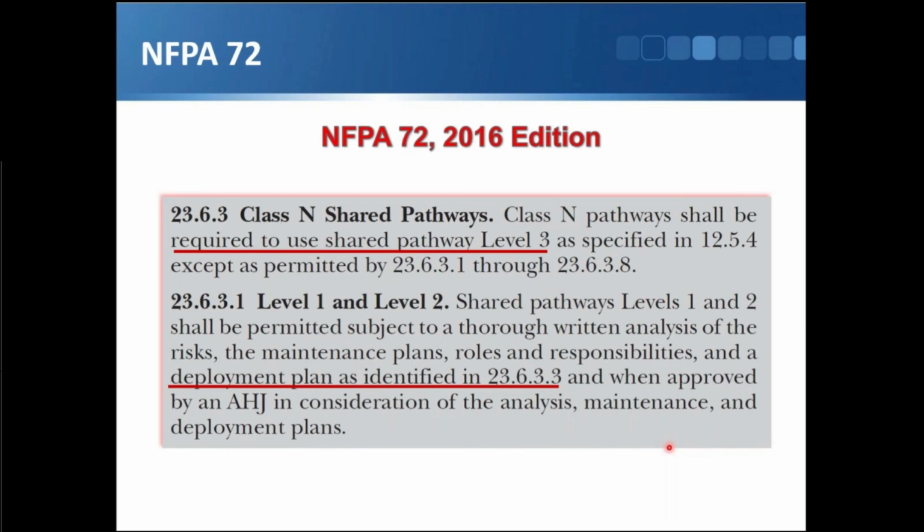All right, so here, in chapter 23, this is where they talk about the SLC circuit basically. So it's other sections that point to these other requirements that were in chapter 12. Here it says that Class N used for the equivalent of the SLC between your panel and your devices has to use level 3.